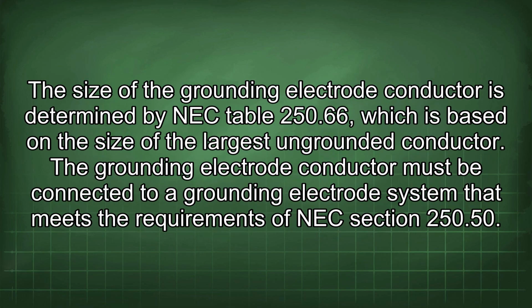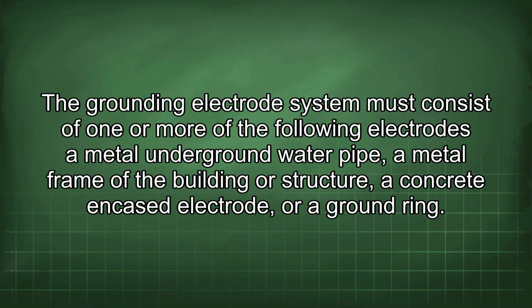The size of the grounding electrode conductor is determined by NEC Table 250.66, which is based on the size of the largest ungrounded conductor. The grounding electrode conductor must be connected to a grounding electrode system that meets the requirements of NEC Section 250.50. The grounding electrode system must consist of one or more of the following electrodes: a metal underground water pipe, a metal frame of the building or structure, a concrete encased electrode, or a ground ring.